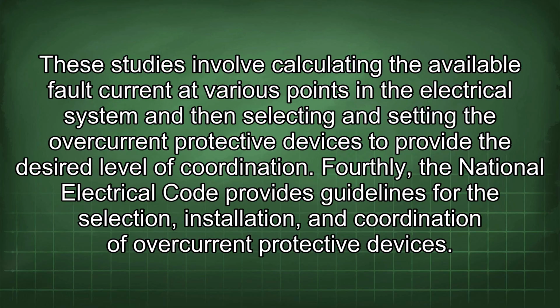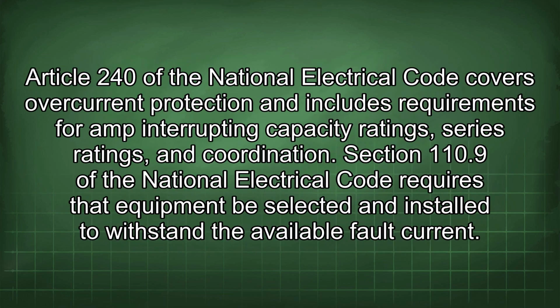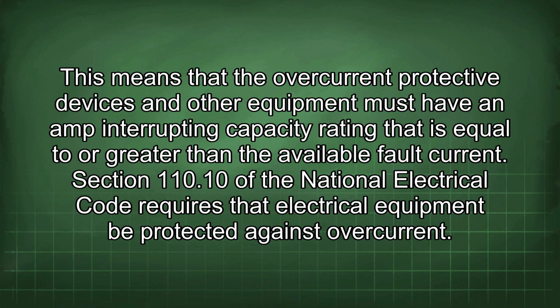Fourthly, the National Electrical Code provides guidelines for the selection, installation, and coordination of overcurrent protective devices. Article 240 of the National Electrical Code covers overcurrent protection and includes requirements for amp interrupting capacity ratings, series ratings, and coordination. Section 110.9 of the National Electrical Code requires that equipment be selected and installed to withstand the available fault current. This means that the overcurrent protective devices and other equipment must have an amp interrupting capacity rating that is equal to or greater than the available fault current.